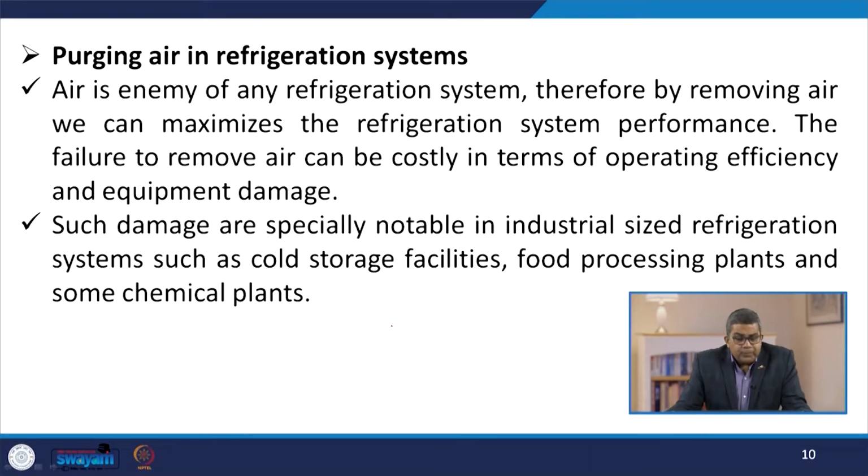Now let's talk about purging air in the refrigeration system. Now air is the enemy of any kind of refrigeration system. Therefore, you have to remove the air in case it is entrapped.